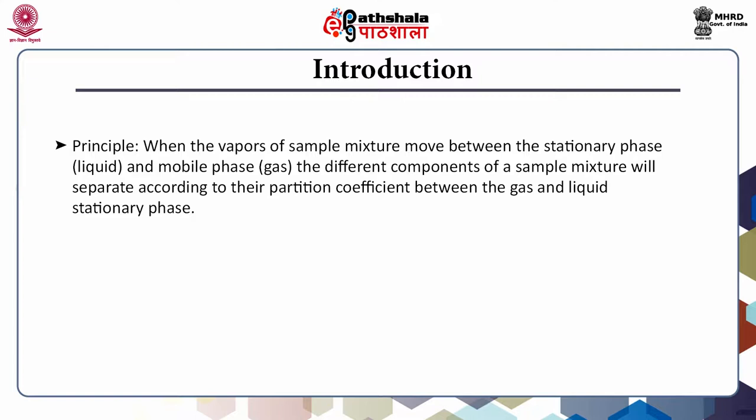This technique is based on the principle of partition chromatography, wherein the components are partitioned between the liquid stationary phase and a carrier gas mobile phase. It involves two active parts: one is the mobile phase, which is an inert gas, and another is the stationary phase, which is a liquid coated on a solid support like silica. The basic requirement of GLC analysis is that the sample should be in vaporized state at a temperature below 350°C. The components of the vaporized sample are fractionated and separated according to partition coefficient between the gas and liquid stationary phase.